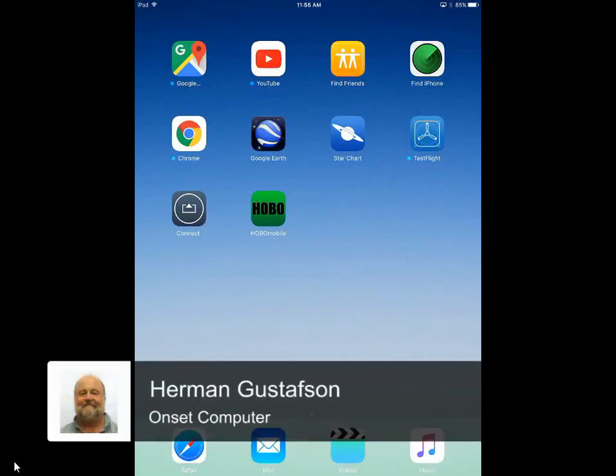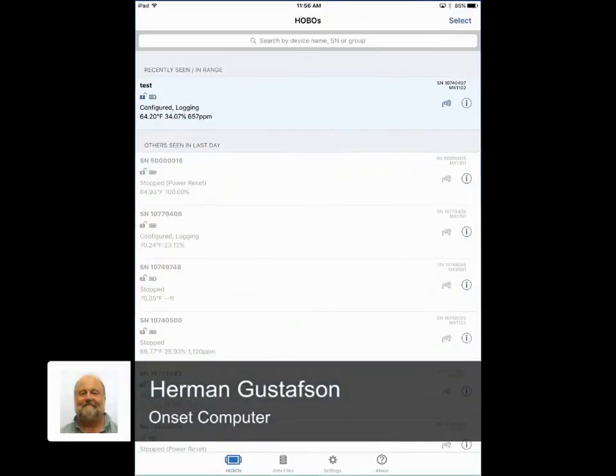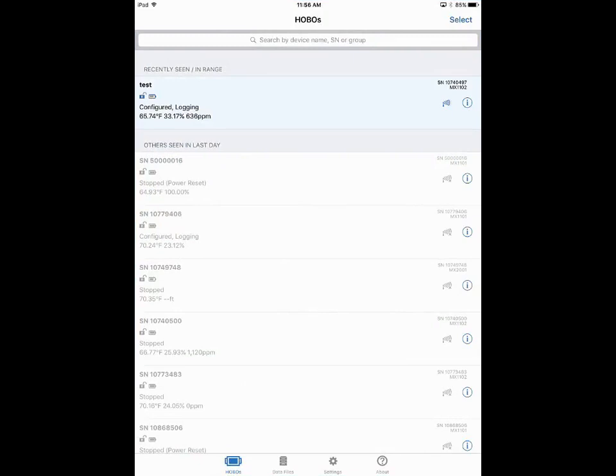Now that we've logged some data with our logger, we're going to connect again. Again, Bluetooth Low Energy does not support streaming data live, so you can't leave your connection open indefinitely. If we had left our connection open, we would get a message that says we're going to close the connection and give you a countdown. It'll ask you if you want to stay connected.